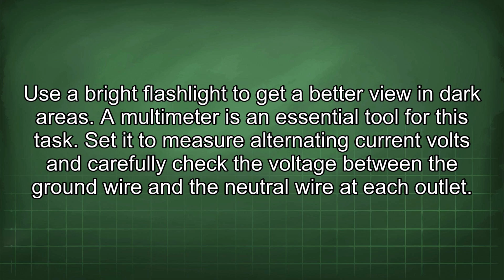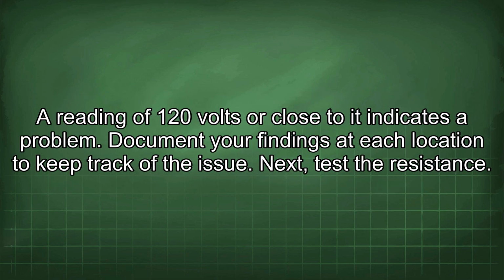A multimeter is an essential tool for this task. Set it to measure alternating current volts and carefully check the voltage between the ground wire and the neutral wire at each outlet. A reading of 120 volts or close to it indicates a problem. Document your findings at each location to keep track of the issue.